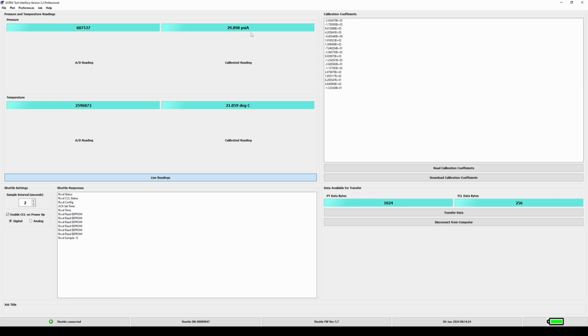But if it's reading 0, 500, or 10,000 PSI, that likely means one of the pins on your pressure transducer is sheared off and the unit probably needs to come back in for a repair. Once you're done looking at the live reading, just press disconnect from computer to get back out. Disconnecting will erase any data on the plunger.